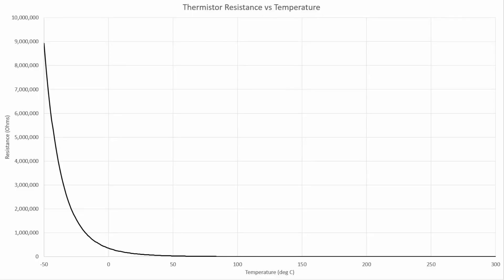To understand how we convert from a resistance tolerance to a temperature tolerance, we need to revisit the resistance versus temperature curve for the thermistor we're looking at. What we're really interested in here is the derivative, or the slope, of the resistance versus temperature curve. I've demonstrated this with three triangles. At very, very low temperatures, a large change in resistance only changes the temperature a small amount — so if our resistance tolerance is large here, our temperature tolerance will still be very small. As we get closer to ambient conditions and then out into our hot end temperatures, a very small change in resistance equals a large change in temperature.